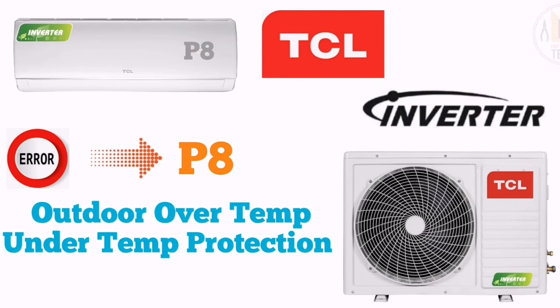When you see error P8, it means outdoor over temperature or under temperature protection, because normally we don't get the P8 error in all regions. If your climate is too cool, if the ambient temperature goes below -1 degree Celsius, or if your ambient temperature is more than 33 degrees Celsius, at that time we get this error.